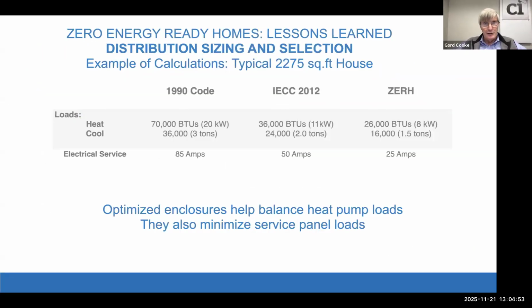What I wanted to highlight is a rethink of what I showed you before. A house in 1990, if you had to heat that house with electric, that's 20 kilowatts—85 amps just to heat the house—versus the zero energy ready heat pump, even with electric backup, is still only 25 amps, which is basically the same as an air conditioner.